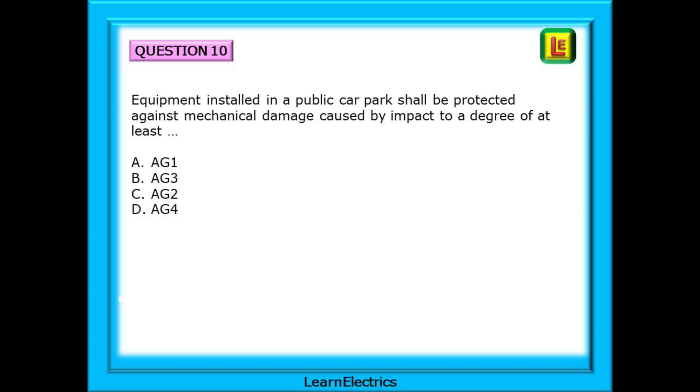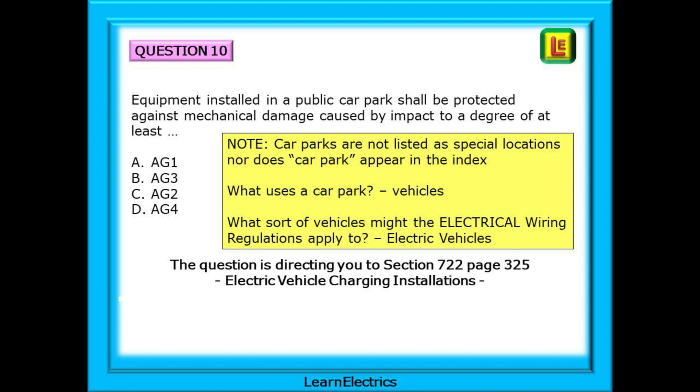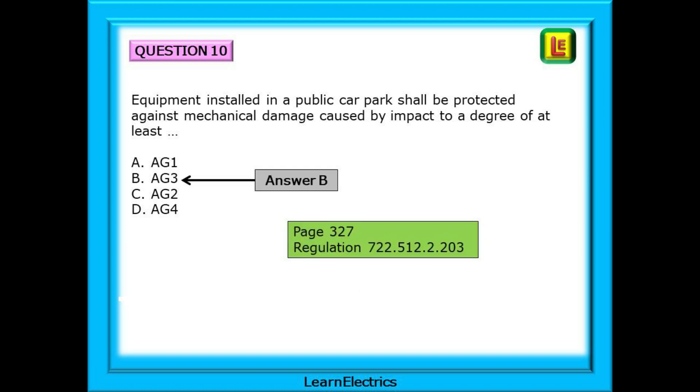And finally question number 10: Equipment installed in a public car park shall be protected against mechanical damage caused by impact to a degree of at least... Note that car parks are not listed at special locations nor does car park appear in the index. But what sort of vehicles might the electrical wiring regulations apply to? It has to be electric vehicles and that is where to look. Page 3 lists section 722 as electric vehicle charging installations and sends us to page 325. On page 327 is the answer. Regulation 722.512.2.203 tells us to choose answer B, AG3.